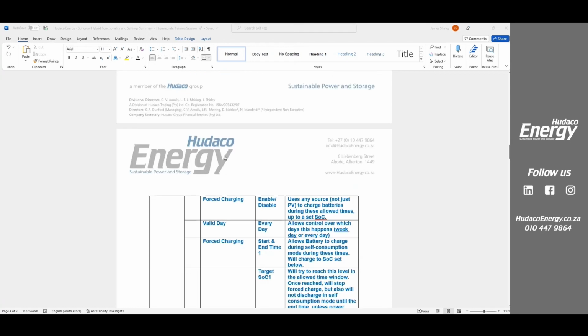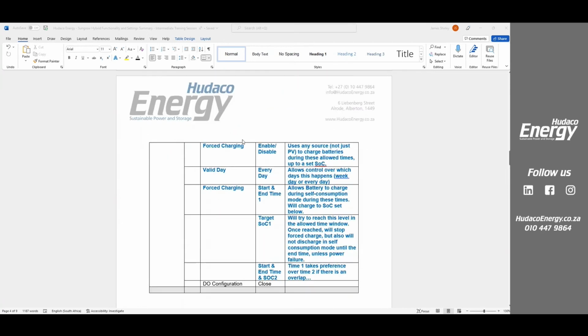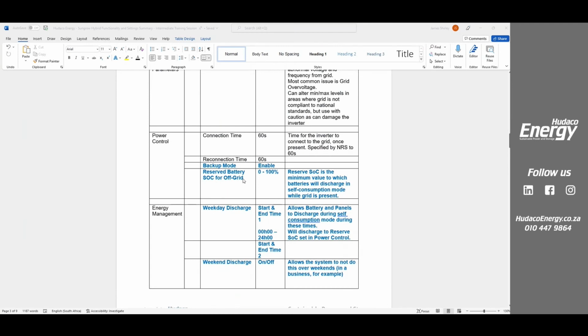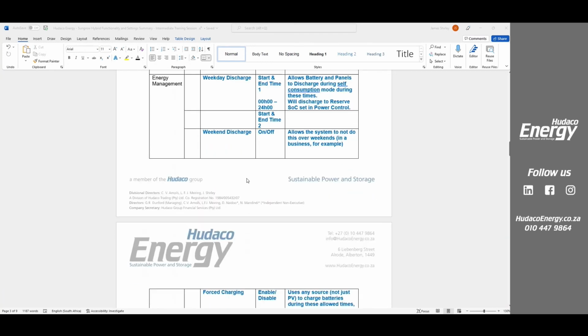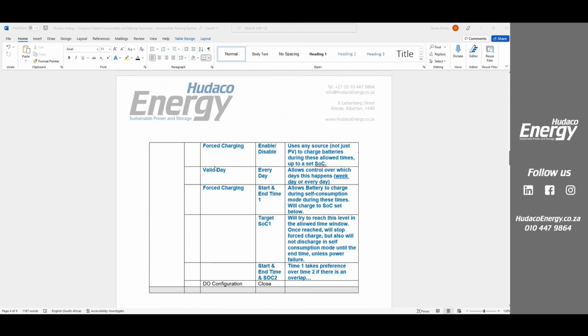You absolutely can. In that case, what you would do is you would just set your forced charging up, or you would set your minimum state of charge up to whatever level you want. So I think in my house, I've got this set to 50% or something like that. And the moment it drops below that and grid returns, it just recharges it to that level. Okay, so you can do it one of two ways if you don't have PV panels. Reserve state of charge, in which case it'll just pull from grid, or forced charge every day and you can charge it to 80, 90, 100%, wherever you want to do that.